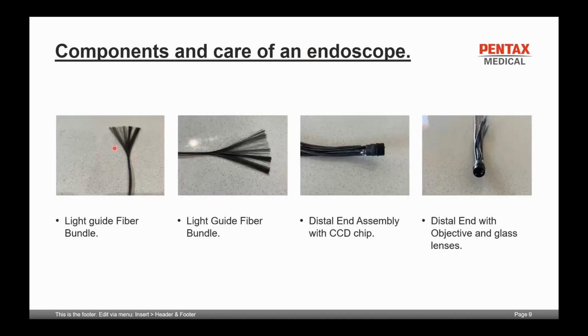This is an example of a light guide fiber bundle. As you can see, it's an exposed light guide fiber bundle. It normally has a cover sheathing that goes over the fiber bundle. And as you can see how delicate the fiber bundles are. There are 2 fiber bundles that run through an endoscope, and they are very, very fragile. So all the stuffing, as you can see in this distal end image over here, there's your CCD position there.